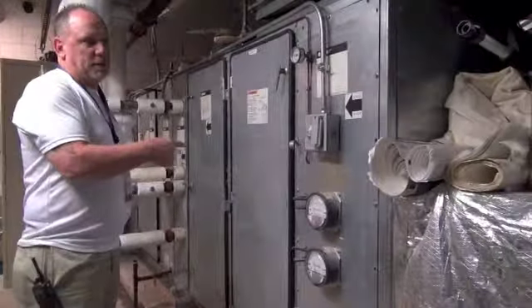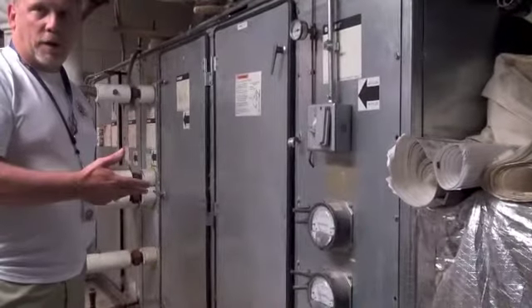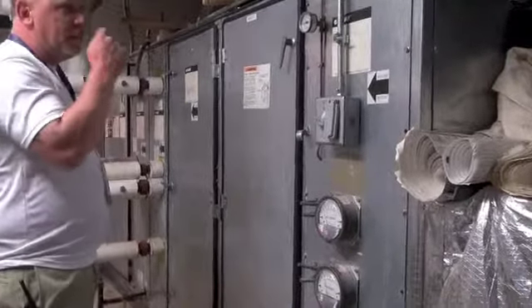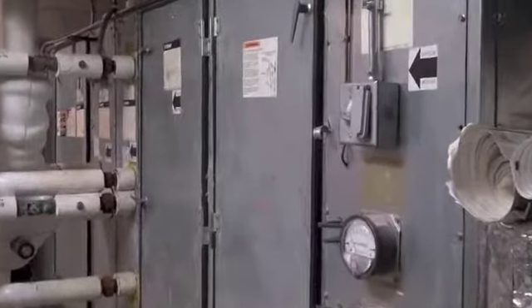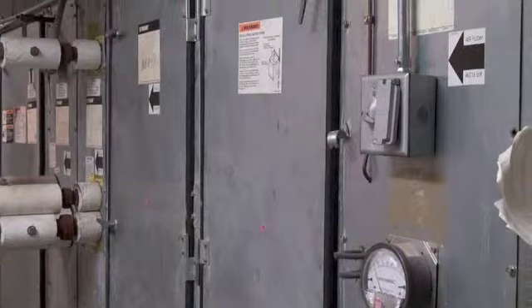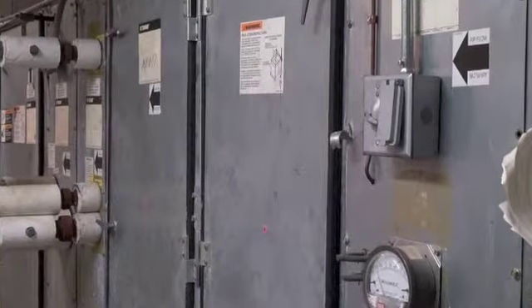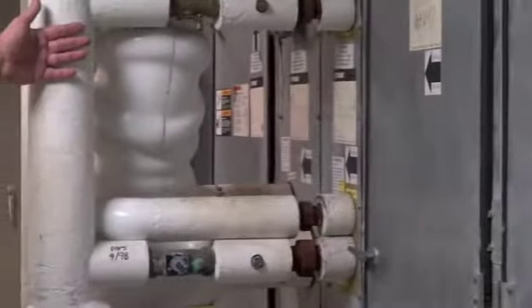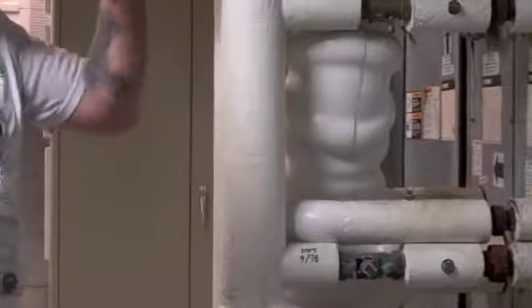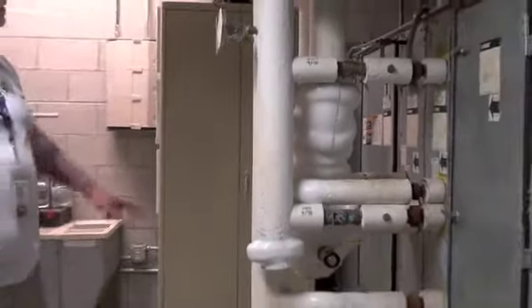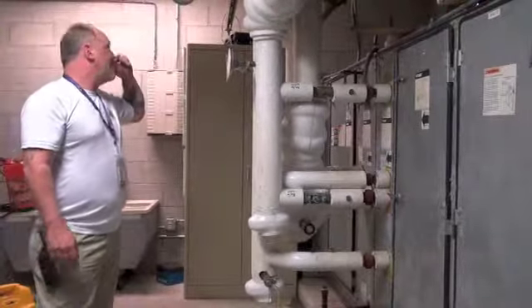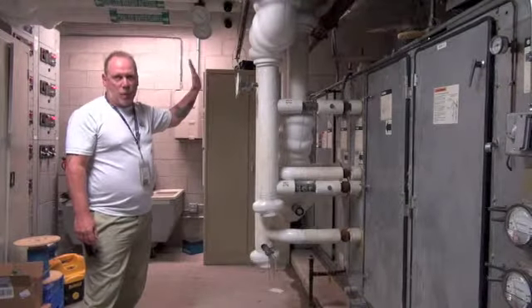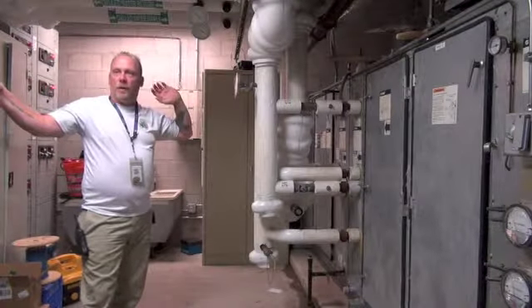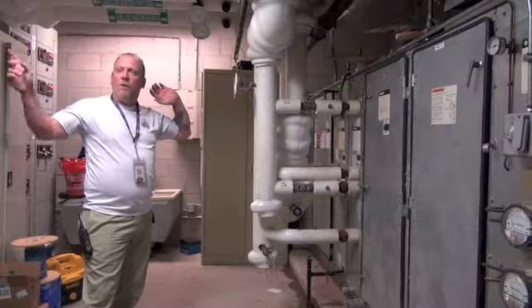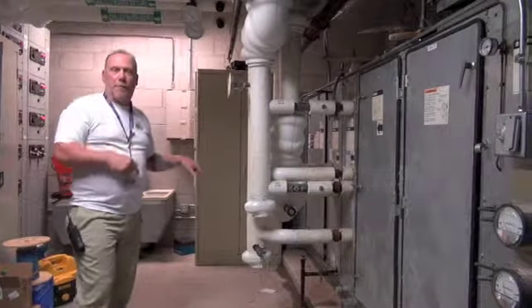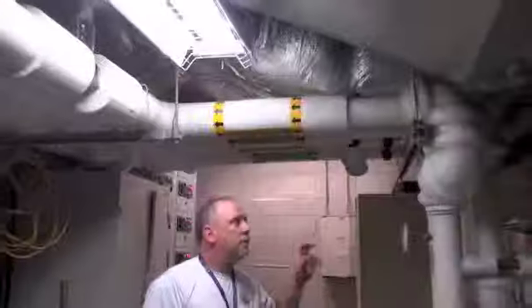This is one of our basic, one of our smaller air handlers in the building. This one here particularly controls the Ravens locker room. It's chilled water coming in. Like I said, it turns back out, goes to Oriole Park, chilled back down. We also have the hot water source, steam. Actually, I'm sorry, this isn't steam, it's hot water. We have a steam converter down in the steam room that converts the steam, heats the hot water, and sends everything back up here as hot water.